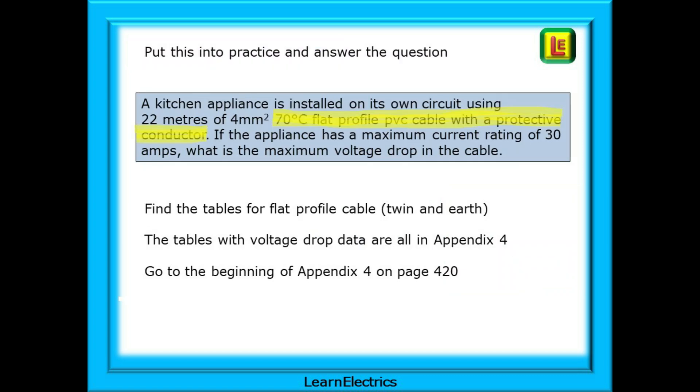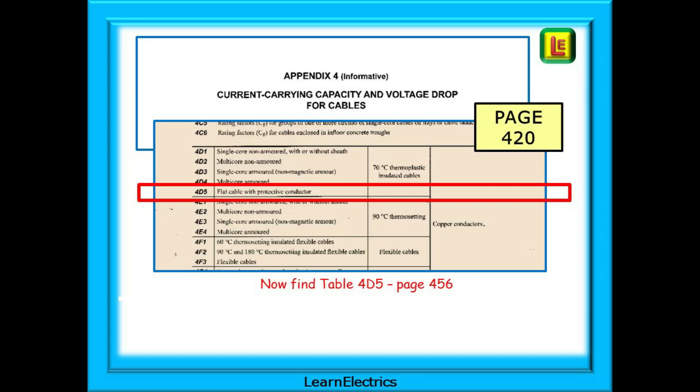Let's put this into practice and answer the question. First of all find the tables for flat profile cable or as we know it twin and earth. The tables with voltage drop data are all in appendix 4 and to find these we need to go to the beginning of appendix 4 on page 420. This is page 420 and the bottom half of the page has a list of different cable types. They all have their own individual tables and we are looking for flat cable with a protective conductor. Table 4D5 is the table that we need but the book does not tell us a page number. It's on page 456 so let's go there.